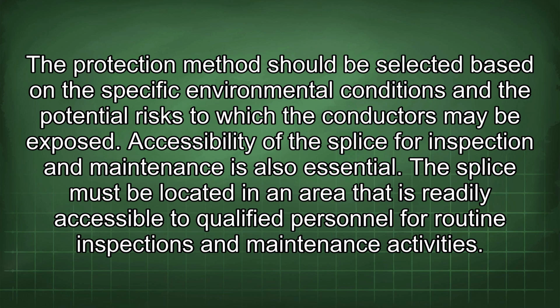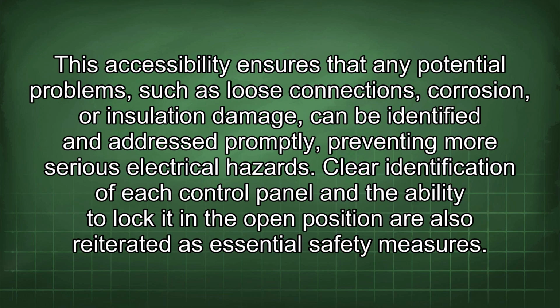Accessibility of the splice for inspection and maintenance is also essential. The splice must be located in an area that is readily accessible to qualified personnel for routine inspections and maintenance activities. This accessibility ensures that any potential problems, such as loose connections, corrosion, or insulation damage, can be identified and addressed promptly, preventing more serious electrical hazards.